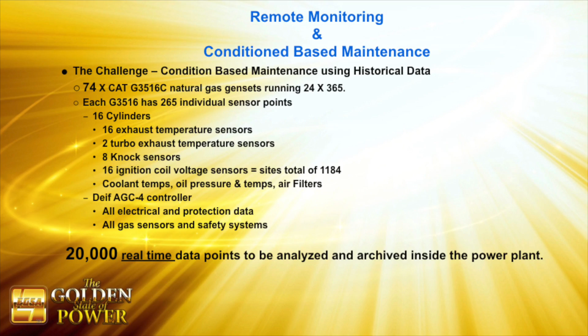Is the knocking on this engine happening too frequently, what are the levels of the knocking, is the restriction on the air filters within specification, are the delta Ps across our fuel filters okay? The gas filters, do we have any gas leaks? You can't look at that with human intervention. You have to use software today. In this example, we're looking at probably 20,000 real-time data points coming in, all being archived historically, but giving us good intelligence and also helping us do predictive maintenance on the engines.